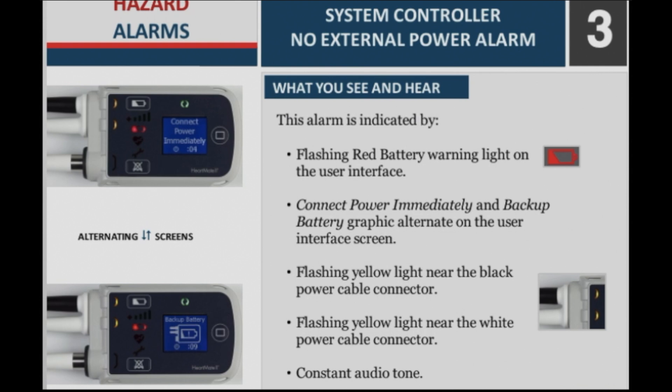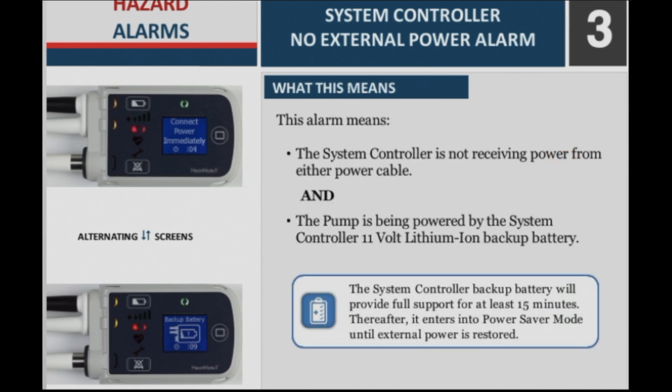Additional indicators include a flashing yellow light near the white power cable connector and a constant audio tone. What this means: The system controller is not receiving power from either power cable, and the pump is being powered by the system controller 11V lithium ion backup battery.